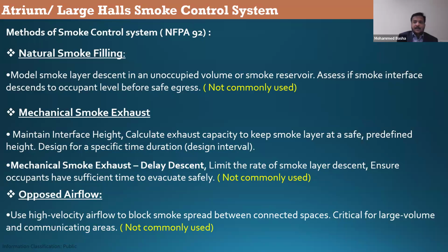Natural smoke filling is not a commonly used smoke extraction method. It's not a smoke extraction method, it's a smoke filling method. Basically, we allow the smoke to build up at the high level. Then we see how long, in seconds, the smoke needs to come down to the occupant tenable height. We need to see that time, and the time for occupant evacuation also needs to be considered.